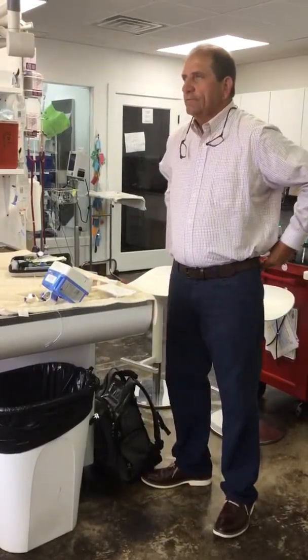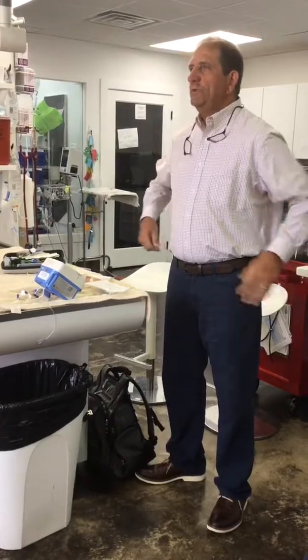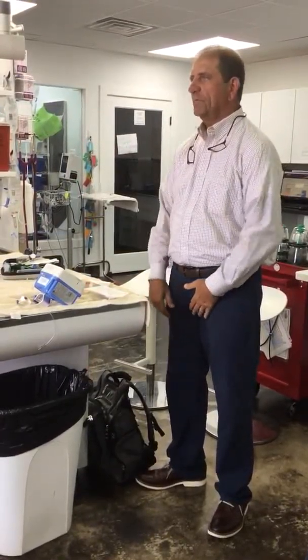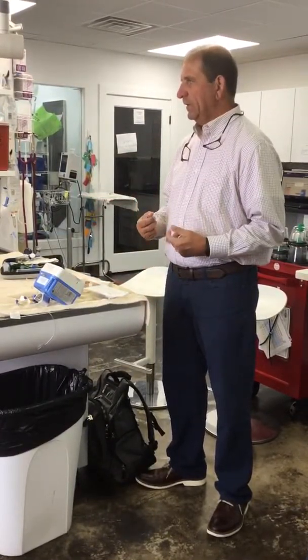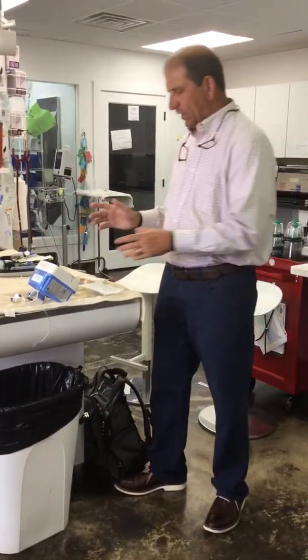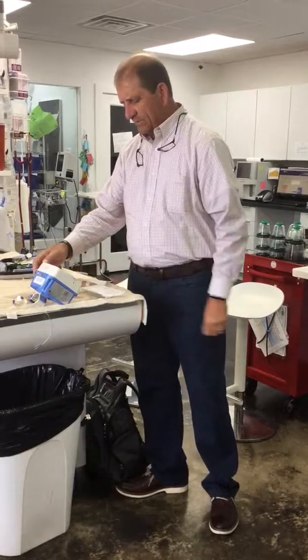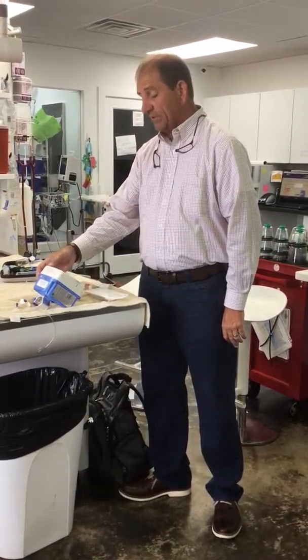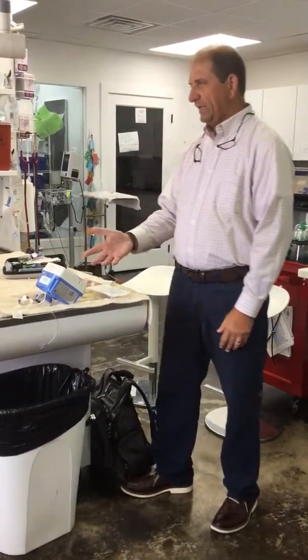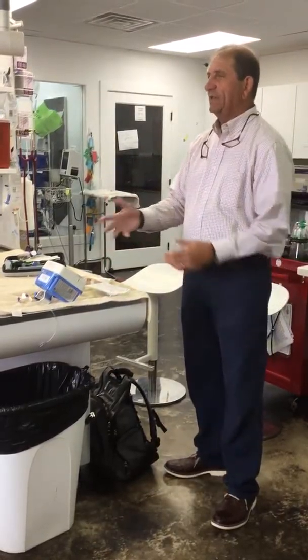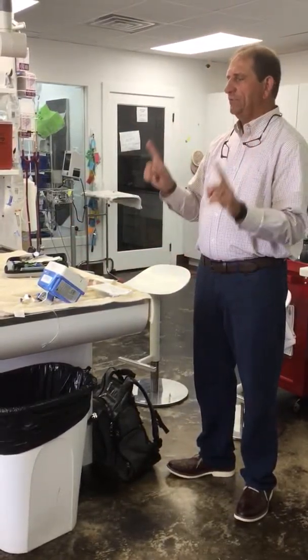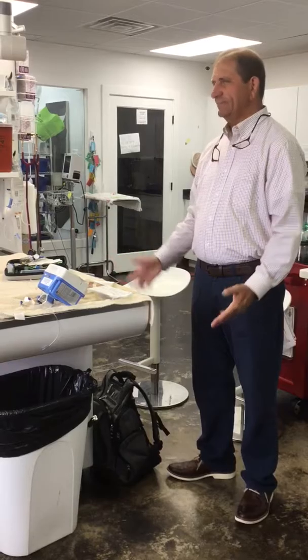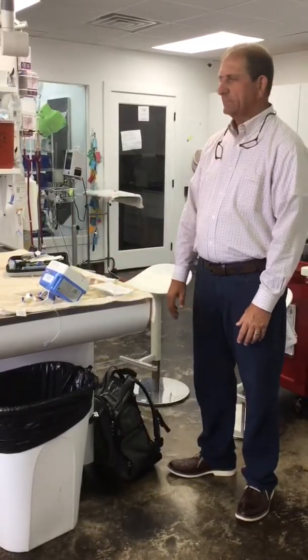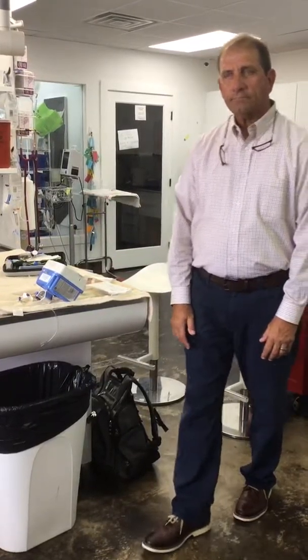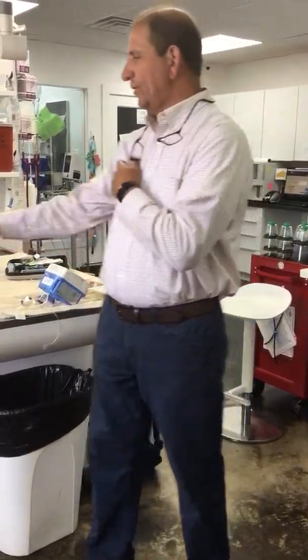So if somebody has a great deal on tubing, some hospital drops off some tubing, something like that, what you do is you call me. And then we'll go over it and we'll see if it needs to be recalibrated. If it does, all I would do, where the tube is, I would click that plus button and it'll go to tube B. And then I would enter that and then I would come back and recalibrate, then you'd have 2 calibrations. You can do up to 10, but I don't know how there's 10. Just turn it off and turn it back on.